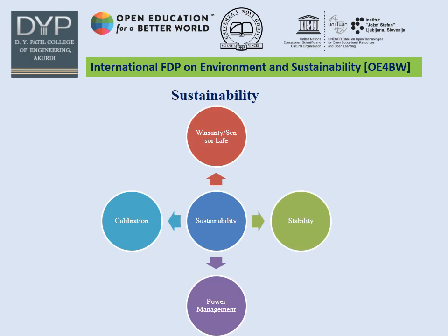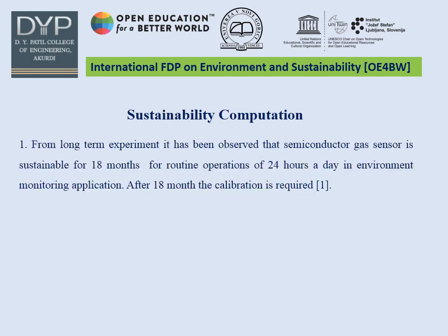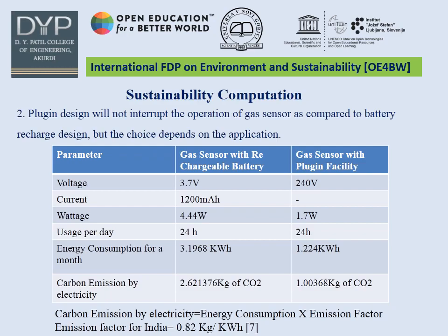There are different options available for powering the gas sensor. The first option is use of a pair of dry cells, the second option is plug-in facility, and the third option is use of rechargeable lithium-ion batteries. For sustainability computation, it has been observed that the semiconductor gas sensor is sustainable for 18 months for routine operation of 24 hours a day in environment monitoring application. After 18 months, calibration is required. A gas sensor with rechargeable battery has a specification of voltage 3.7V and current rating 1200 mAh, giving a wattage of 4.4W.